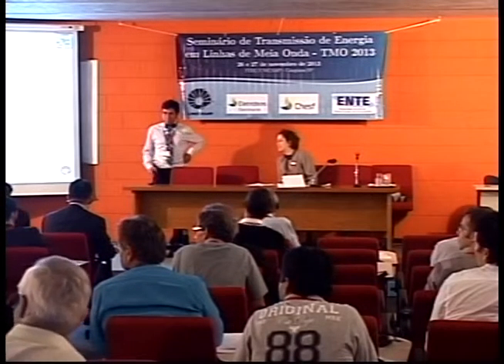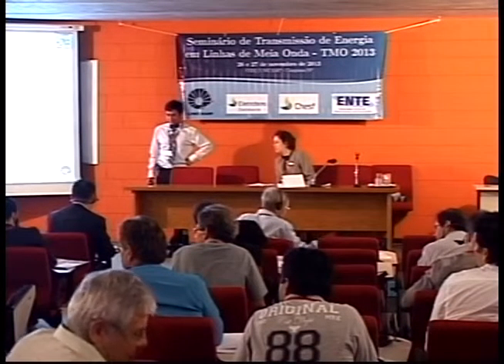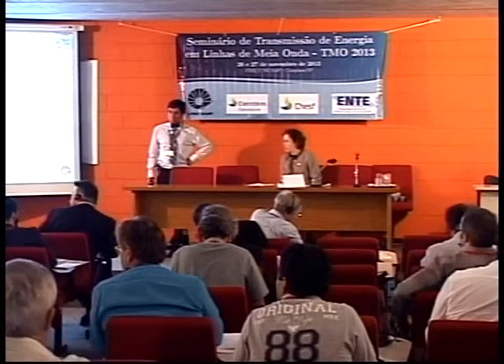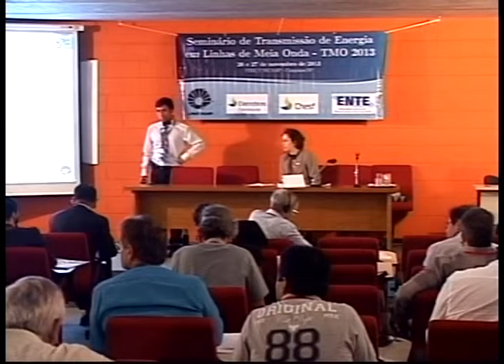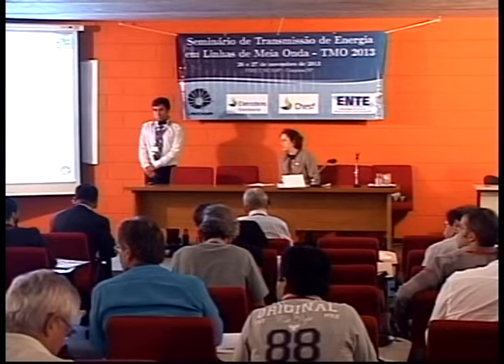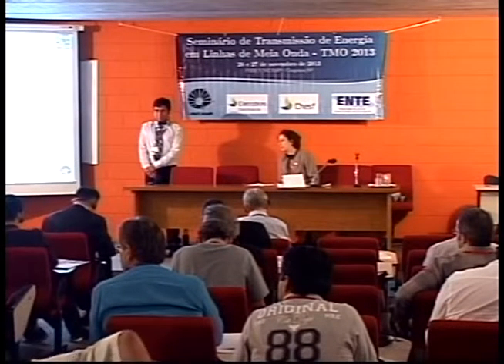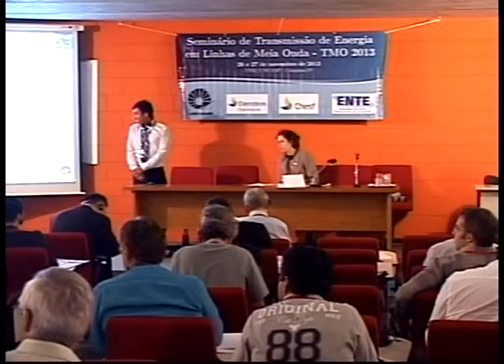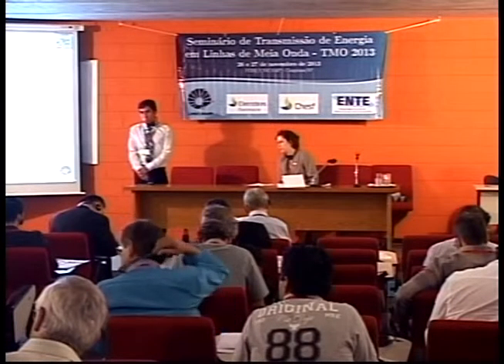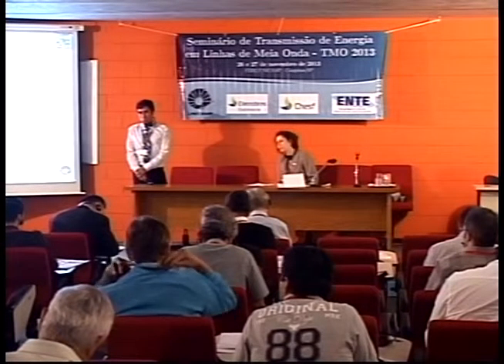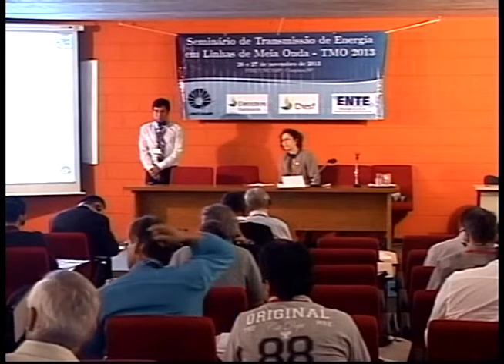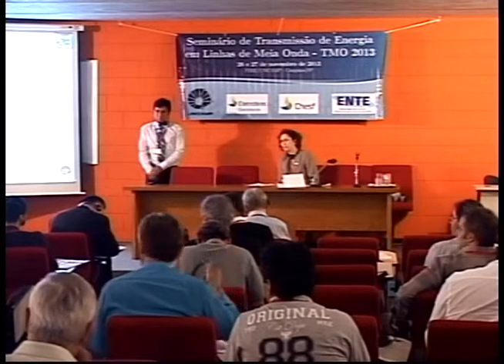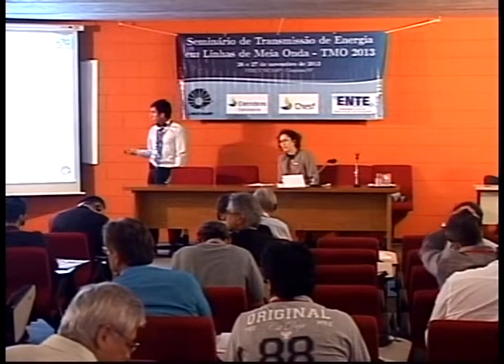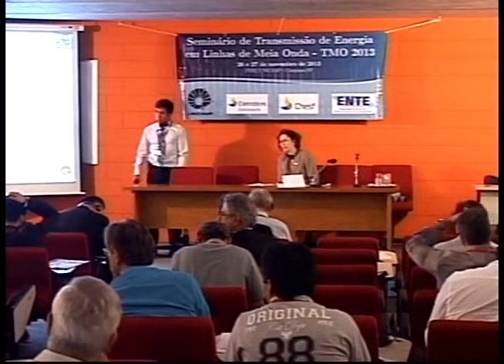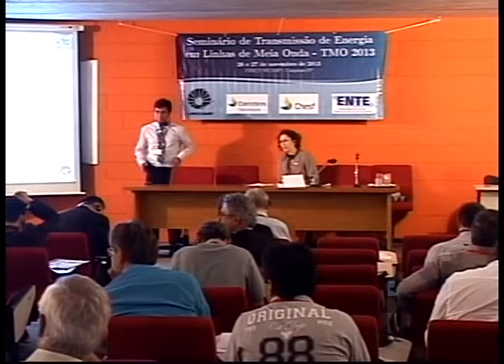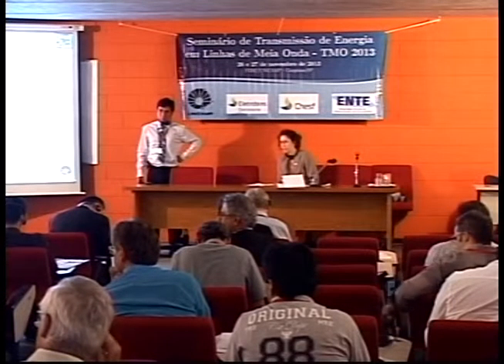Cristina, the thing is, since yesterday I have a question I didn't want to take home today. And now, with this difficulty of sensing failures at the central part of the line, trying to use the existing relays and so on, I become more anxious. I know that on one side you either do it with the existing surge arresters, or you can't do the energization test. This question has been bothering me since yesterday. All studies are being performed taking into account that energization will have to be done in this part, and only then with the shunt compensation turned off, but the surge arresters will have to be present.